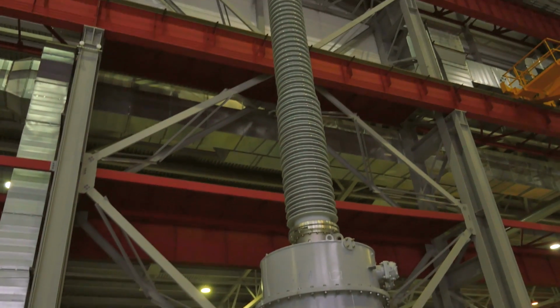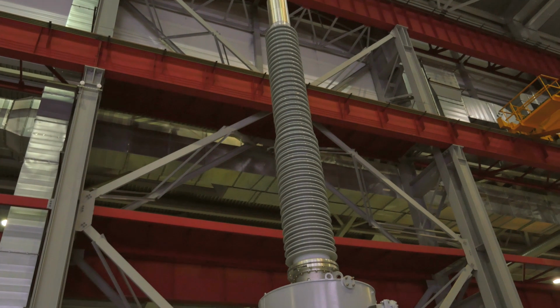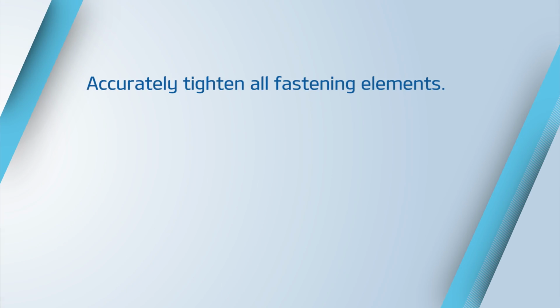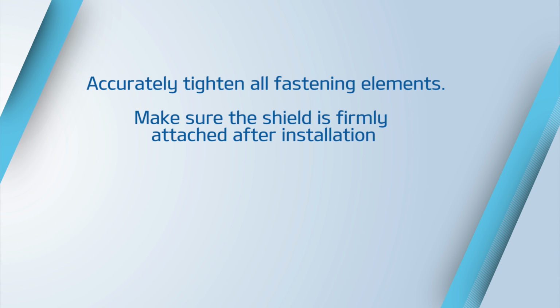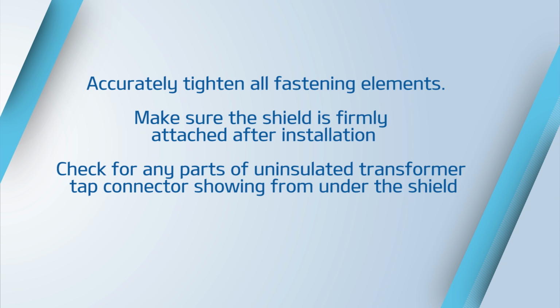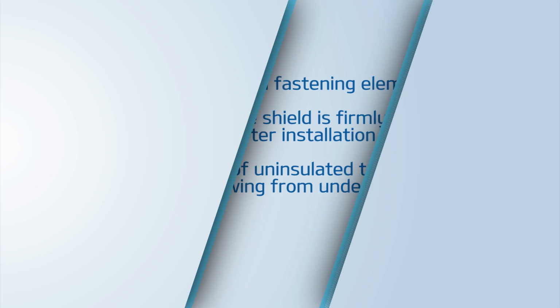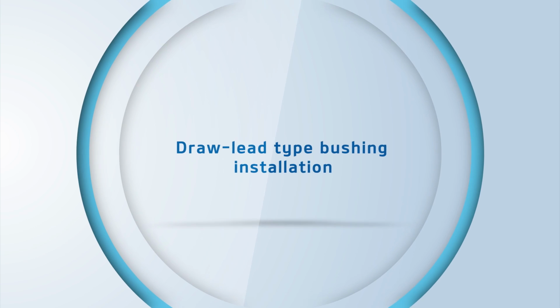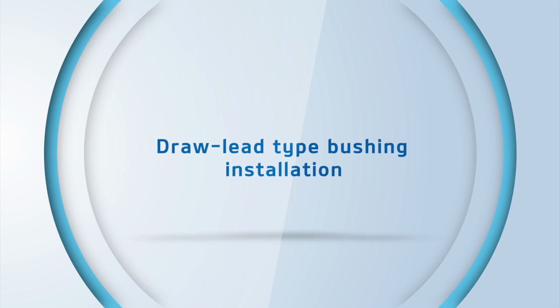Thus, we have reviewed the bottom terminal bushing installation. Let's repeat the key points. Accurately tighten all fastening elements. Make sure the shield is firmly attached after installation. Check for any parts of uninsulated transformer tap connector showing from under the shield. Draw lead type bushing installation.